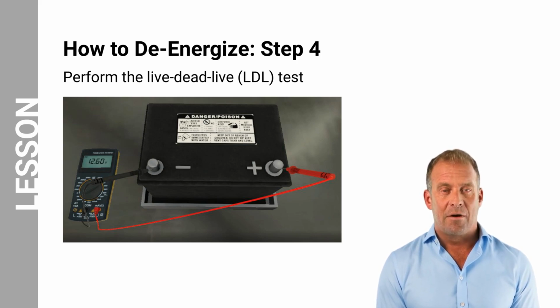Locate a known good battery, preferably on a workbench or another safe and stable surface. Connect the red test lead to the positive terminal and the black test lead to the battery's negative terminal. The digital multimeter should display the voltage reading. In this case, it should read around 12.6 volts for a fully charged battery. After confirming the voltage reading, turn off the digital multimeter. When the de-energization process is complete, repeat this process to ensure that all meters and adapters are functional and undamaged.